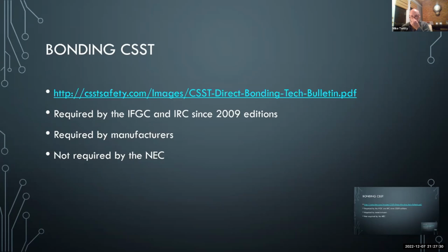My opinion, people ask about the CounterStrike, the TracPipe, the black insulated CSST. In my opinion, it's best practice to bond all of it. The manufacturers have it listed as okay, with the conductor in that insulation, but it's not that big a deal. I require to bond all of it, and there's not really any exception in the IRC that says they're exempt from that. Of course, you can have that argument, manufacturer's specs as opposed to code. But anyway, if you can look that up, we're not going to go into detail on CSST tonight.